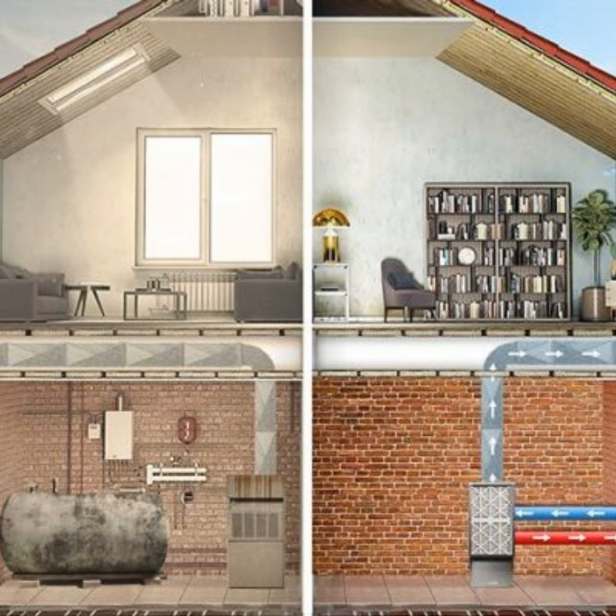Based on how much heating or cooling the home needs, we'll figure out how much ground loop we need to install. The ground loop is a thin plastic pipe, about 1.25 inches in diameter. So it's not very wide, but it extends 300 to 500 feet down into the yard. So it goes quite deep. And it's shaped kind of like a bobby pin. You can think of this long, thin pipe that has a hairpin turn at the bottom and then comes back up right next to the part going down. That allows water to circulate down into the ground, then turn around and come back up.